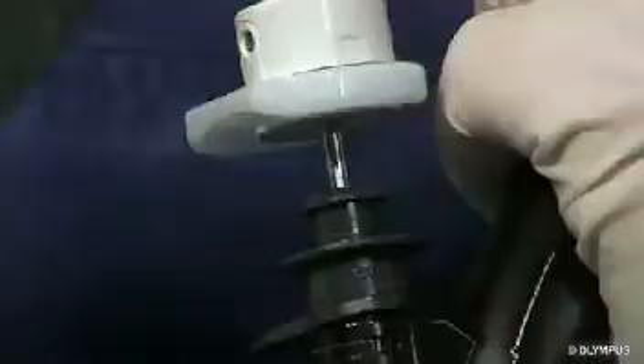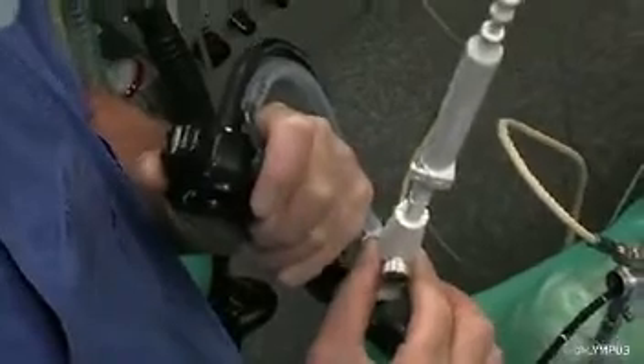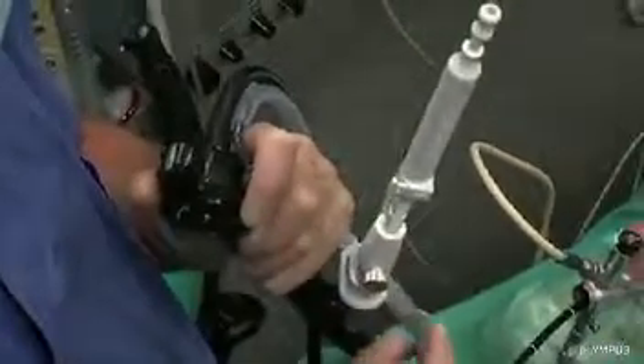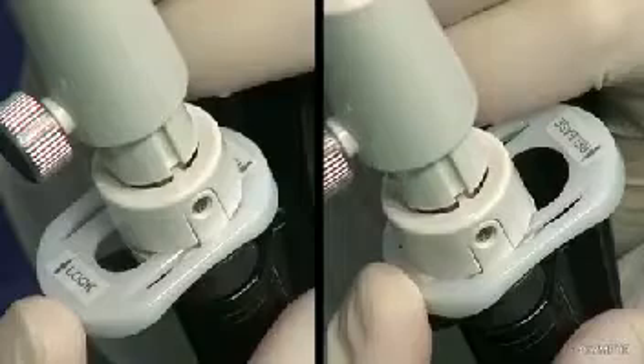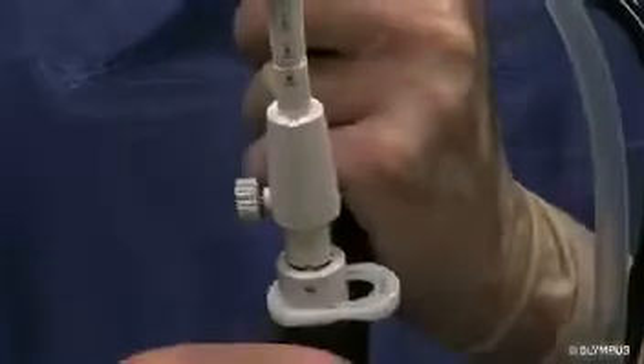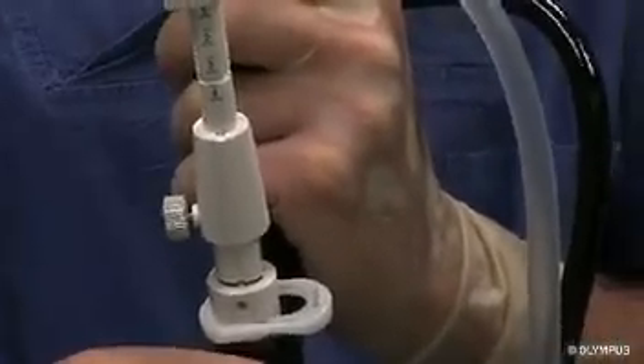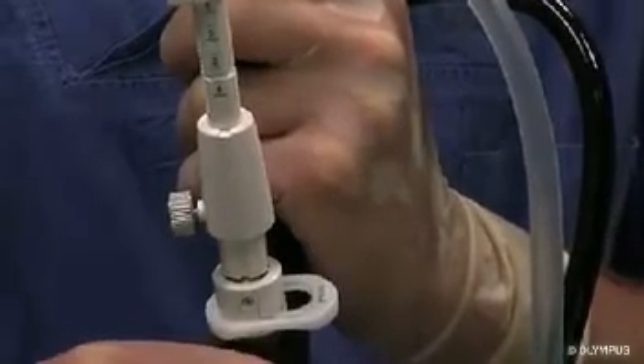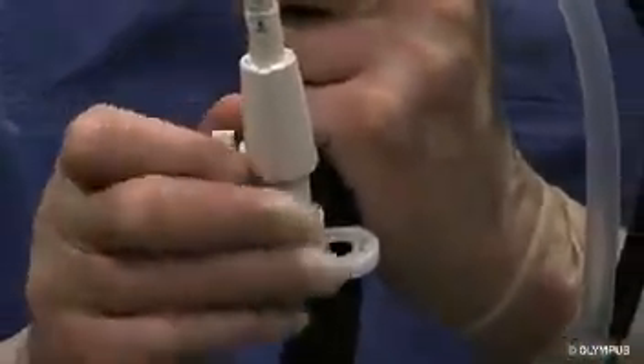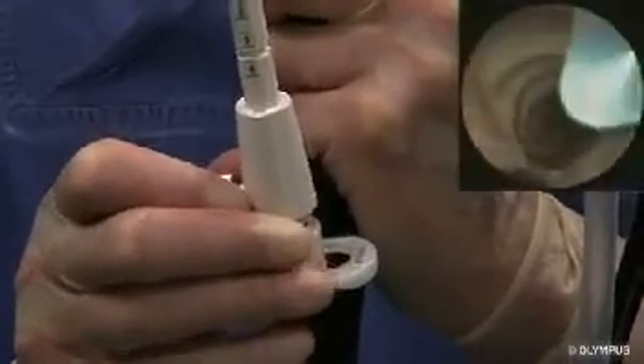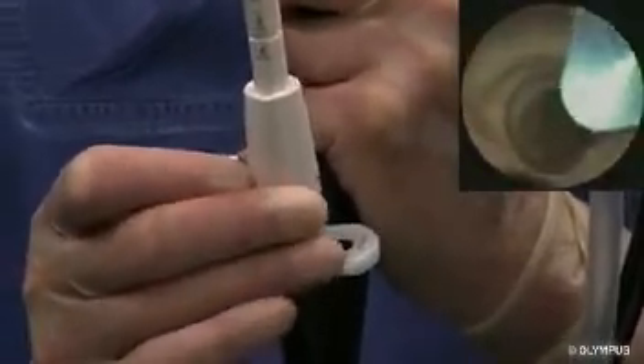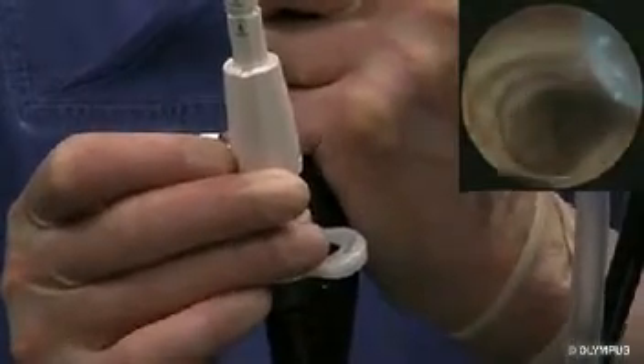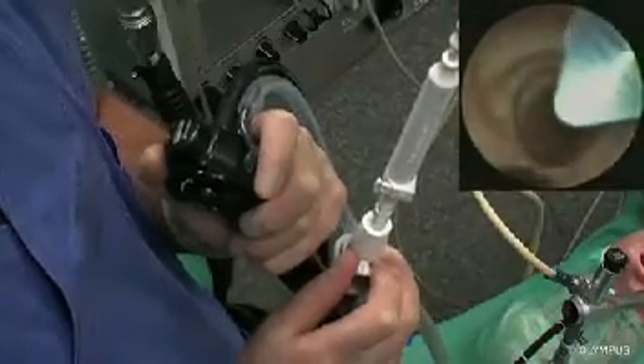Check that the connector sits firmly on the adapter biopsy valve. Then push the connecting slider over the sleeve of the adapter biopsy valve to securely connect the needle system with the endoscope. If in doubt, check the indicators on the connecting slider. Care has to be taken that the needle sheath is inserted far enough distally so that it extends beyond the end of the instrument channel in order to protect the instrument channel from damage during the procedure. The adjustment is done by moving the connector section while the sheath position is controlled endoscopically.